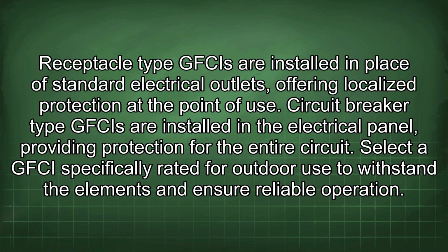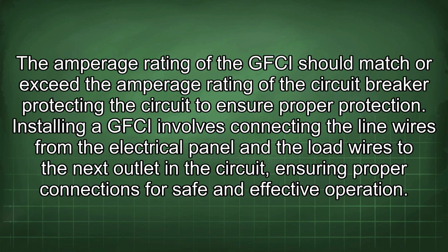Select a GFCI specifically rated for outdoor use to withstand the elements and ensure reliable operation. The amperage rating of the GFCI should match or exceed the amperage rating of the circuit breaker, protecting the circuit to ensure proper protection. Installing a GFCI involves connecting the line wires from the electrical panel and the load wires to the next outlet in the circuit, ensuring proper connections for safe and effective operation.